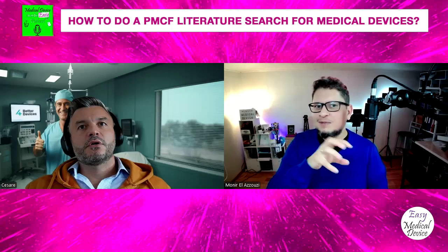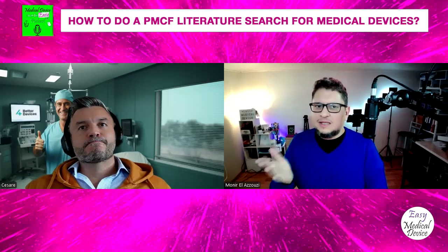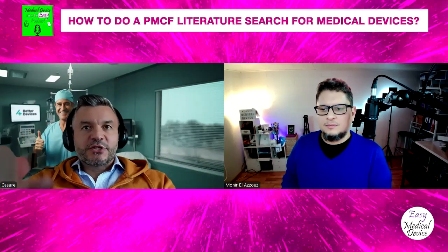Like when we are doing a design, for example, we are starting with risk management as an initial phase. Is there a best time to start this research? All these processes are a bit of loops, but for me the pyramid is always the intended purpose. The intended purpose branches down into what you have to do for the state of the art. So typically the medical background, and then the specific systematic review on the intervention or the alternative intervention. That's the state-of-the-art part with its quantitative summaries.